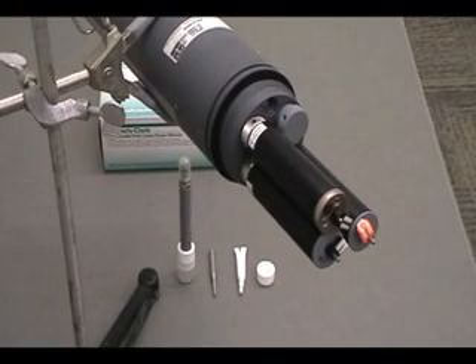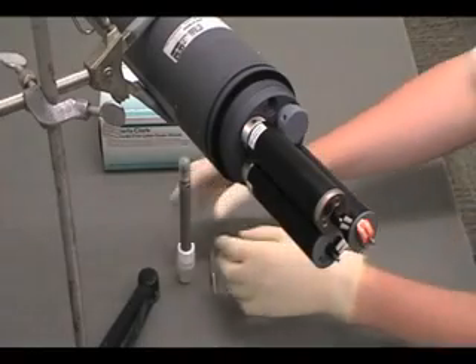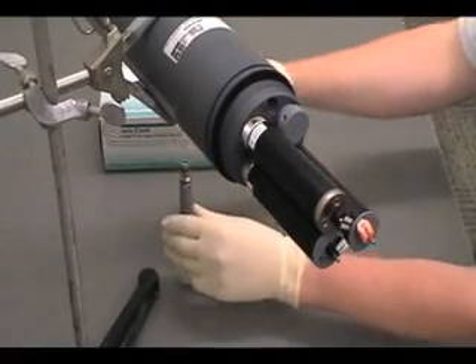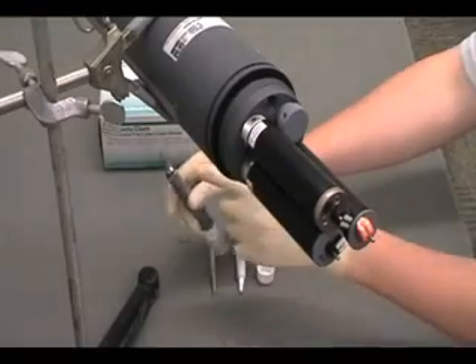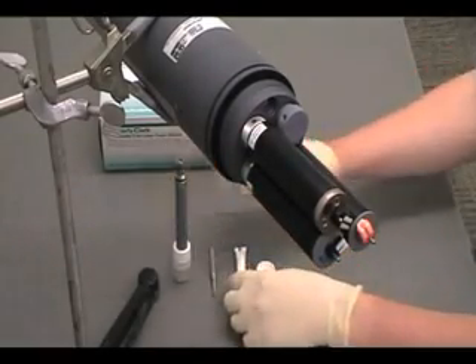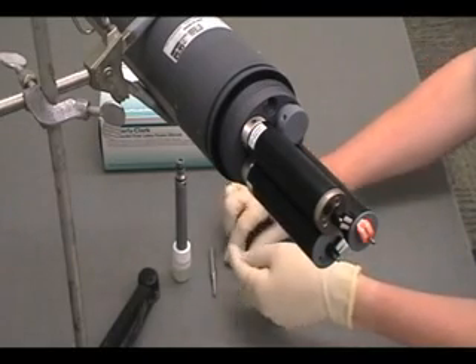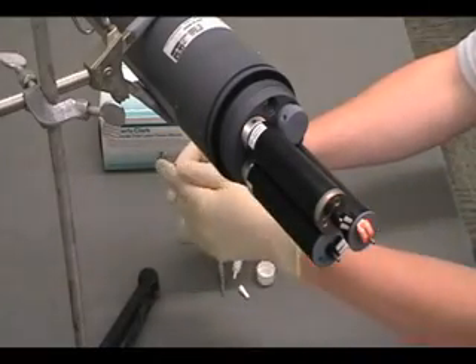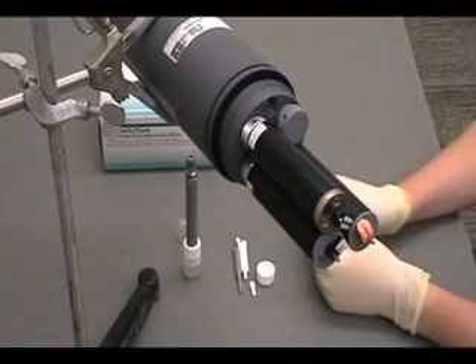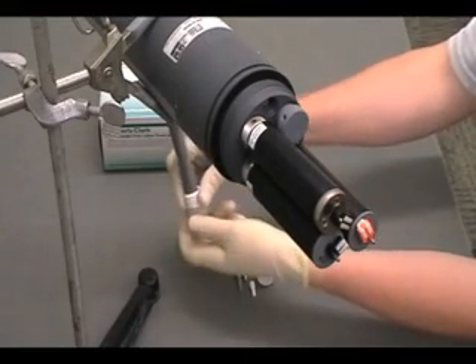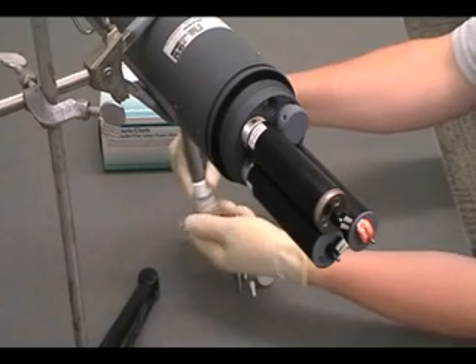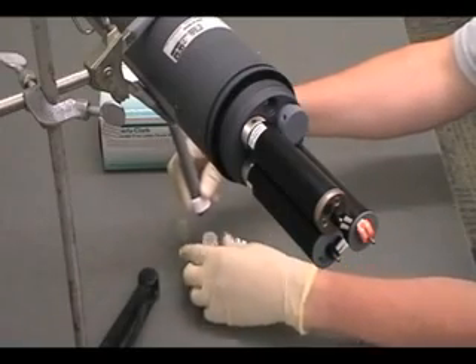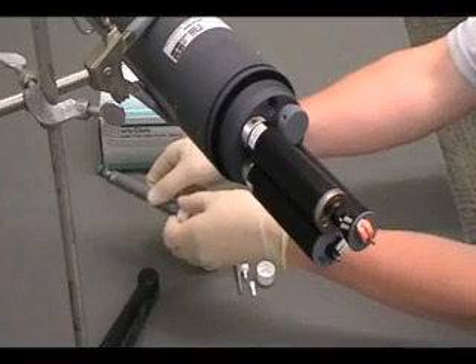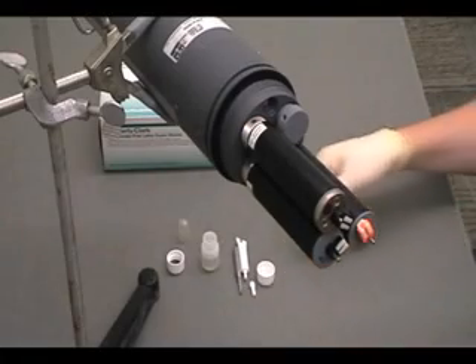As another example of how to insert a regular sensor, we will now insert the pH and oxidation reduction potential probe. For this procedure, you will need to put on protective gloves. Remove the cap from the electronics end of the pH ORP sensor. Ensure that the O-ring on the sensor is completely clean of dirt. Apply a very light sheen of Krytox to the clean O-ring. Remove the sensor from the electrolyte solution by unscrewing the cap. Remove the cap and O-ring. Close the bottle with the second cap.